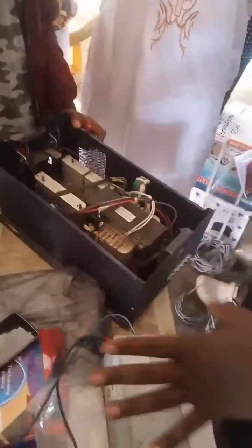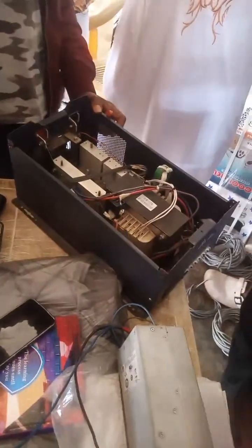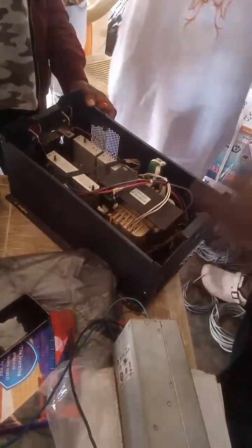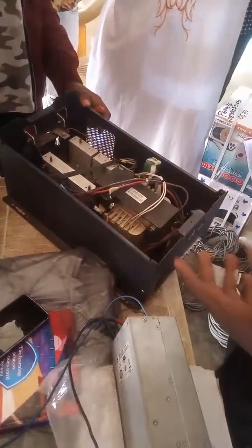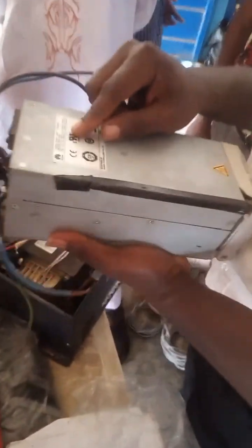The 20 amps on average means it will take 10 hours for your battery to be full. There are some environments that you know can't have 10 hours of electricity. Maybe they are having 5 or 6 hours, and you want your client's battery to charge faster. You don't want only this to charge it. You can use this rectifier. If you want the specification, this rectifier can supply up to 50 amps.